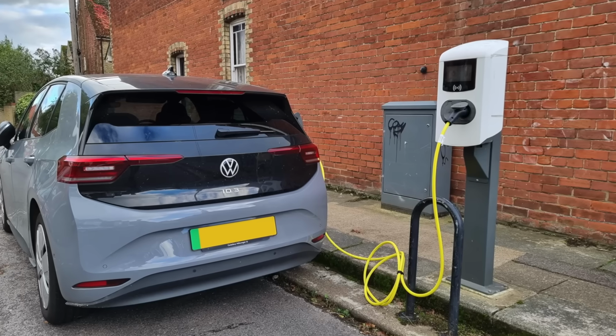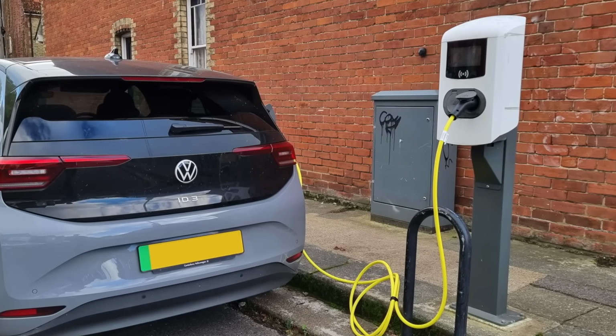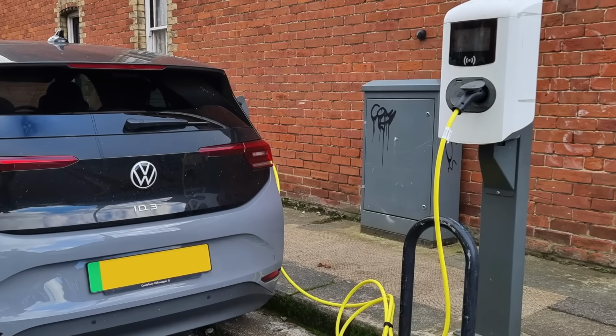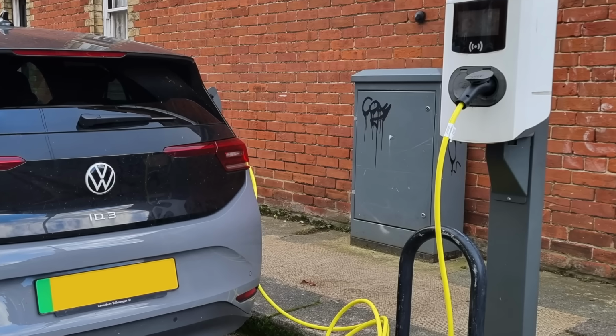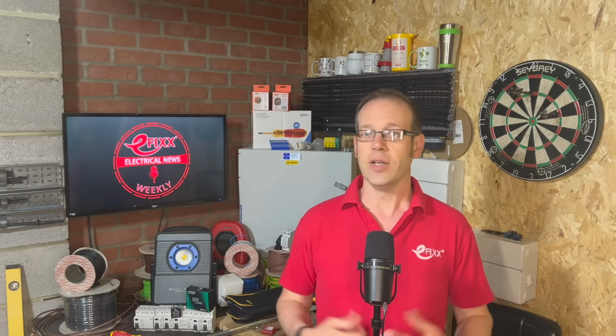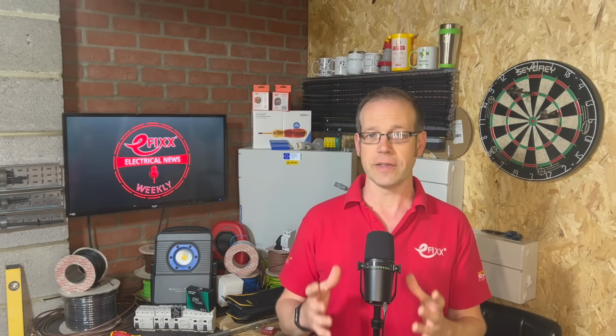The alarm stems from the possibility of simultaneous contact between the body of electric vehicles and another vehicle or a piece of street furniture, such as a metal lamppost or telecoms cabinet. Unless the two items are connected to the same distribution systems, there's a prospect of a fault of a high potential difference between them.